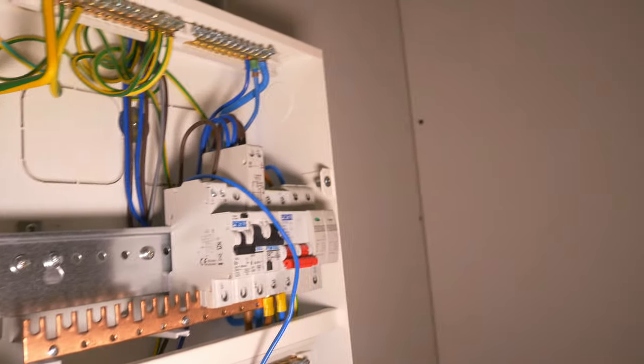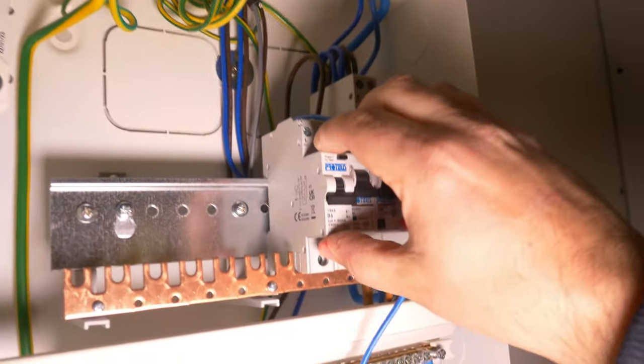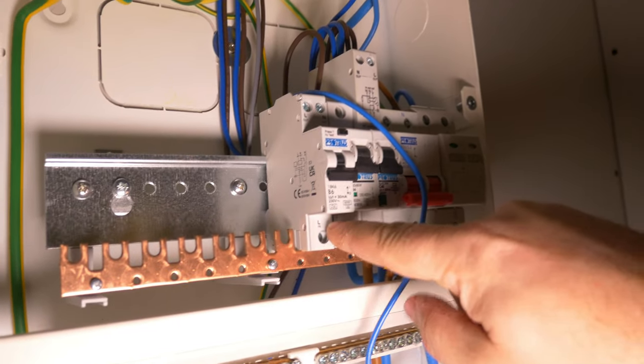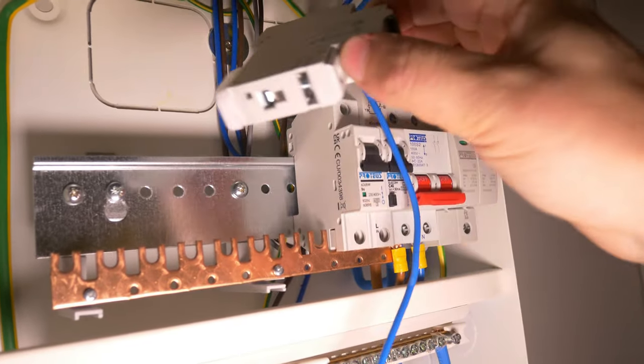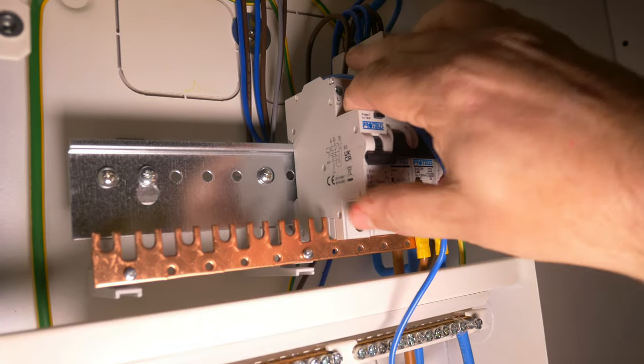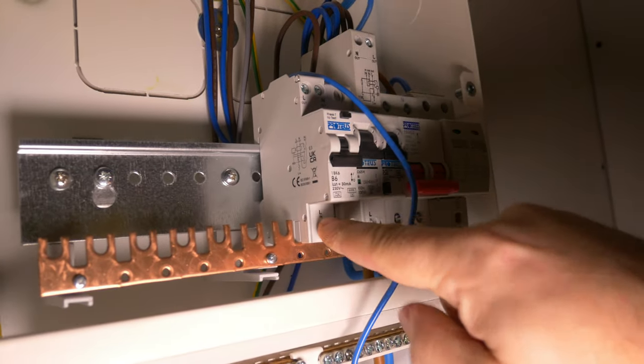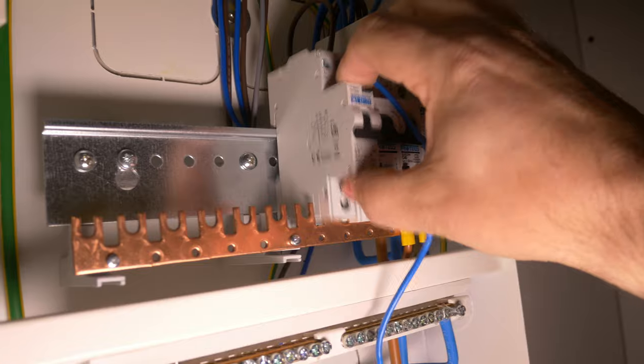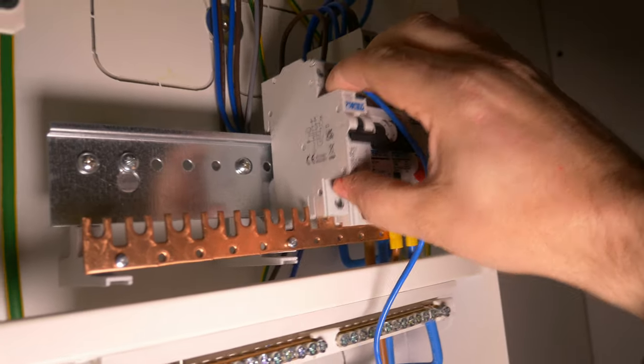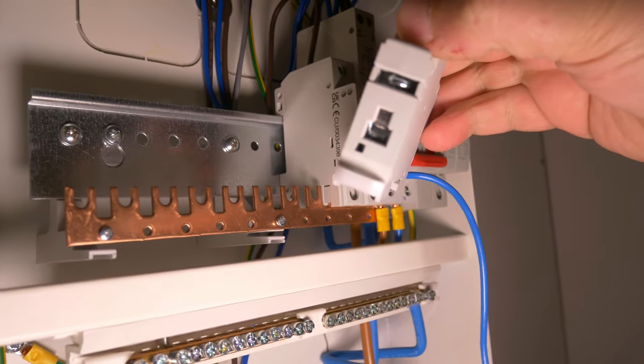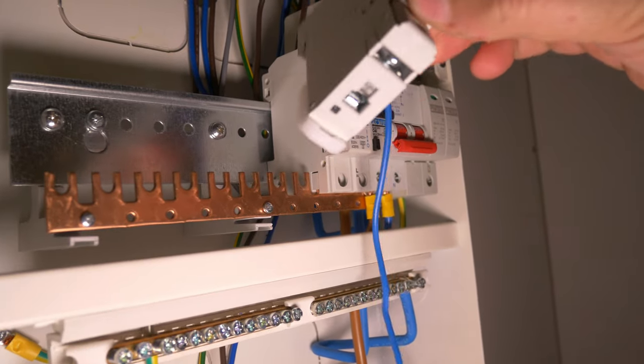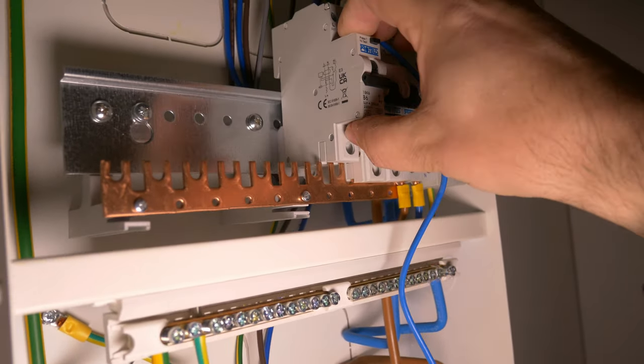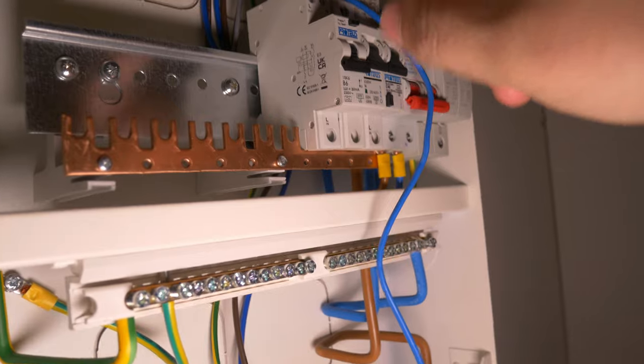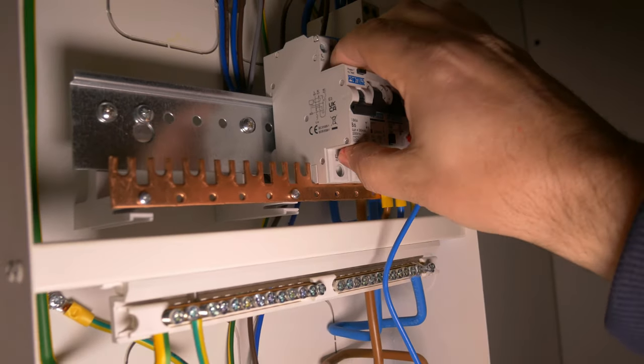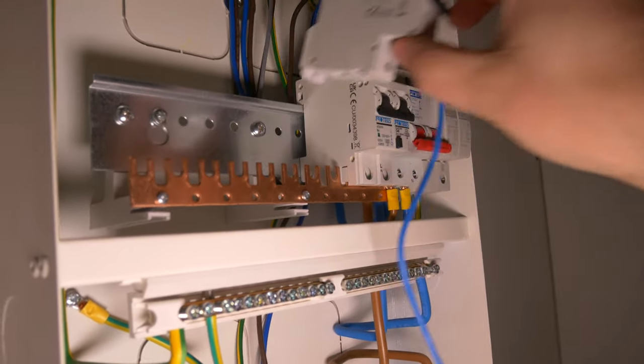So just to cover off the removal of the RCBO, so it works for all these devices, simply loosen the front screw and then it will just lift out. It doesn't actually lock itself into position underneath, it's fastening itself on this front screw. So if it moves about, you know you've not got it on there right, whereas with the cage clamp method, sometimes you can miss it and you've got to check very carefully with other brands because it would lock on to the underside of the DIN rail, and you can have it feel secure whilst it's not actually connected. But that one's easy to remove.